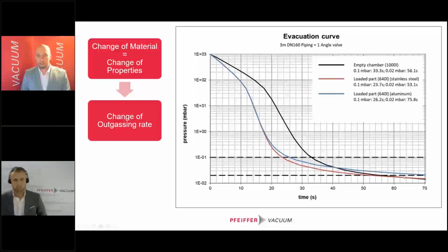This is nothing you can really influence on your own. You have to consider this when initially installing or conceptualizing your pumping group, as the material of the part you test will most often not change through the lifetime of your system.